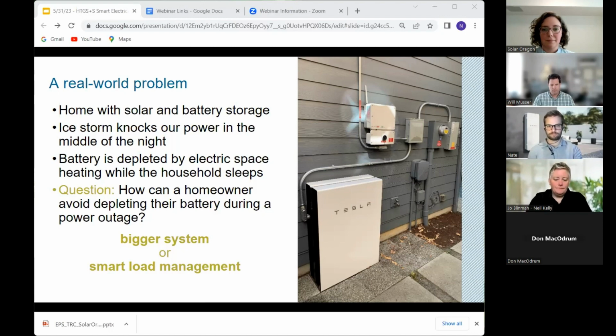Once the utility connection switched off, the battery jumped in to manage the home's electric loads. Given that outside temperatures were below freezing, maintaining the thermostat's minimum overnight temperature of 66 degrees was a big lift for the heat pump, which in turn drew down the battery as the occupants slept. When they awoke, the temperature in the house was nice and toasty, but the battery was completely depleted.